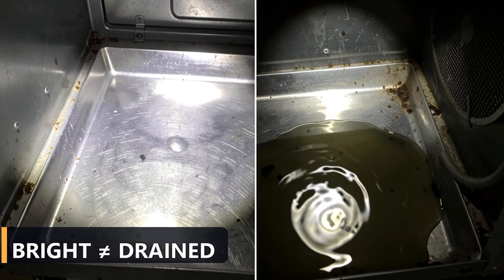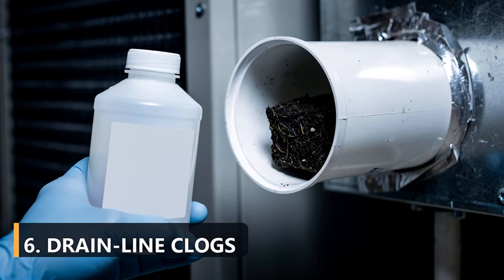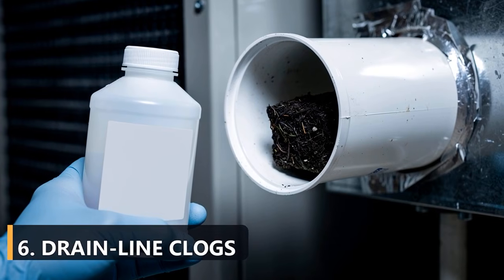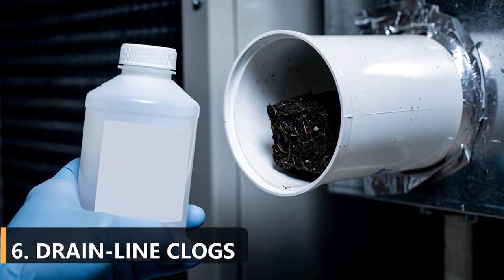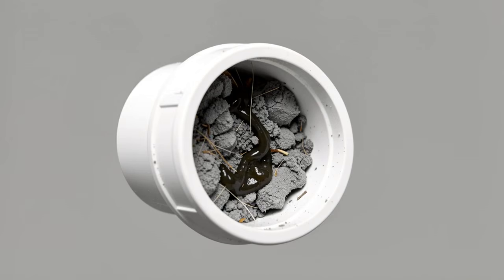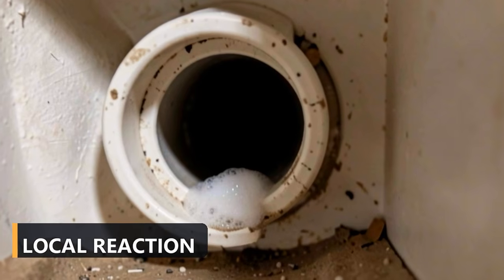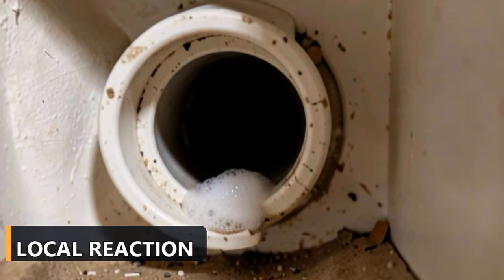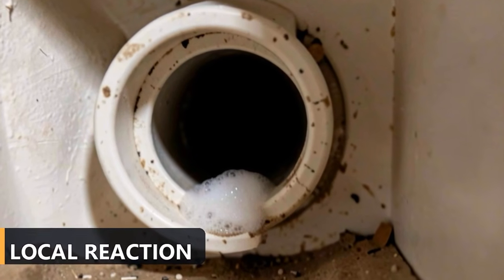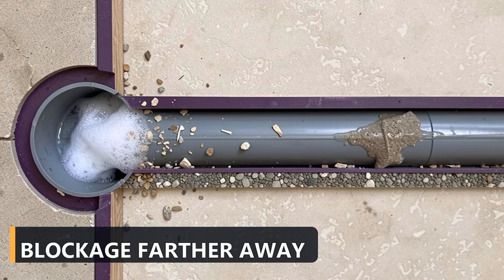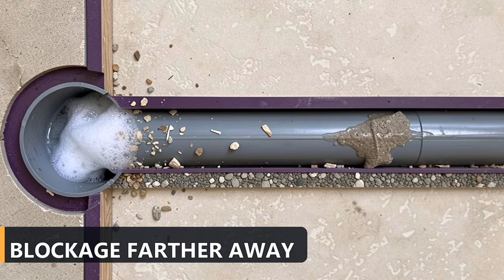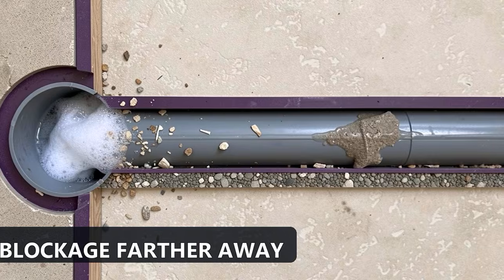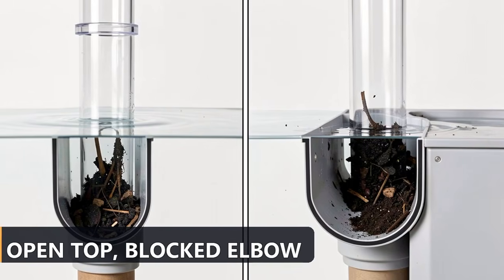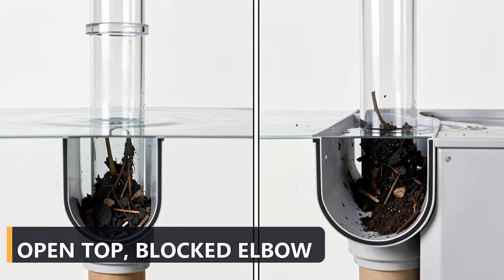Number 6. Pouring peroxide into a clogged condensate line can move the problem without removing it. A drain line clog is often a compact mixture of dust, slime, algae-like growth, and debris. Peroxide may react with organic material near the access opening, but it cannot guarantee that a blockage several feet away has been cleared. Expanding foam can loosen fragments that travel farther down the pipe and settle at an elbow. The top appears open while the restriction simply changes location.